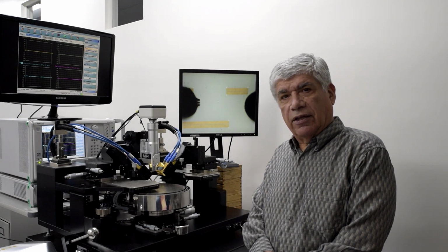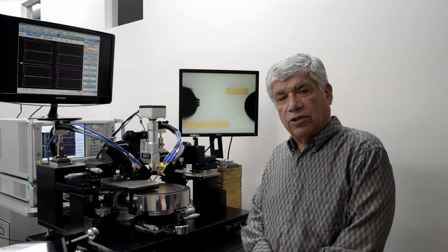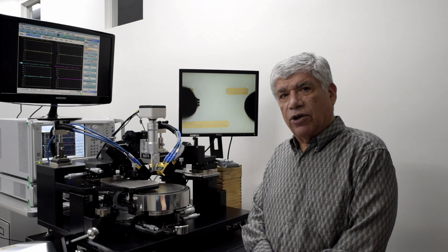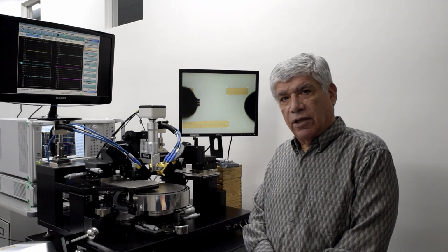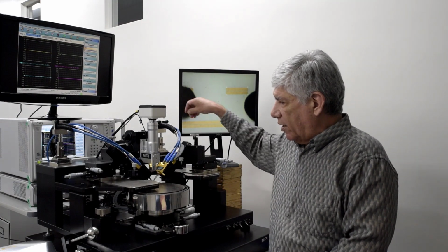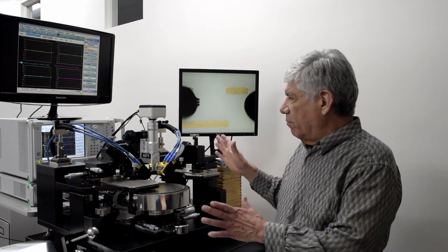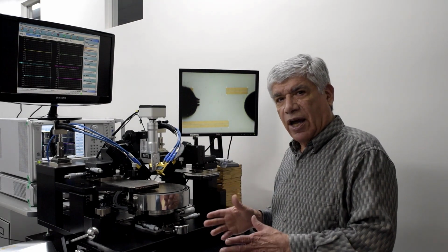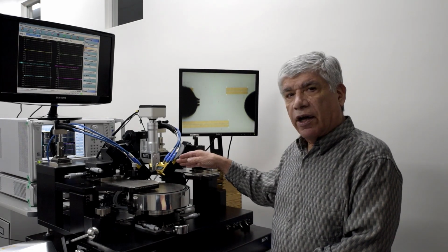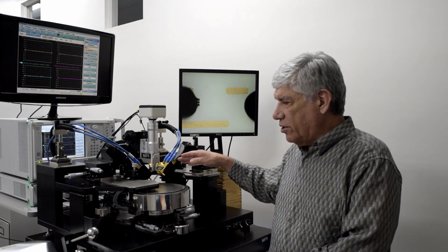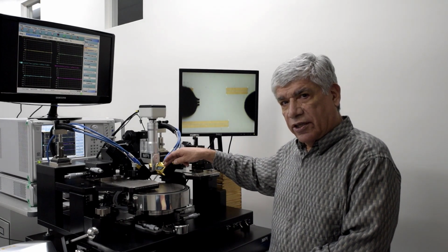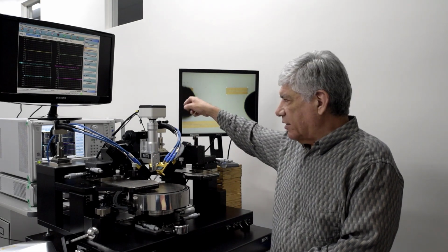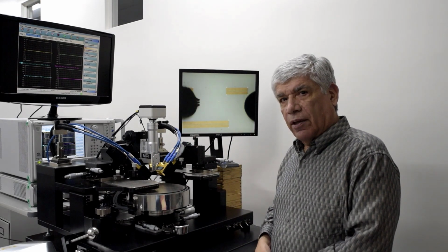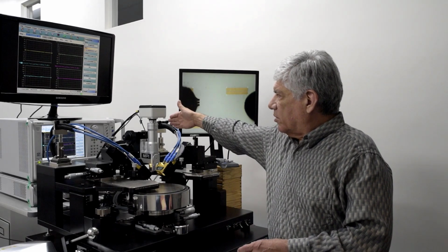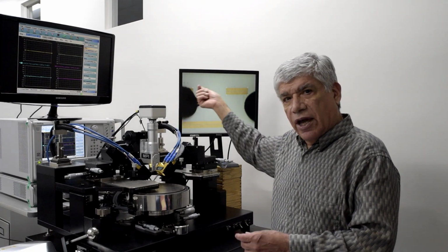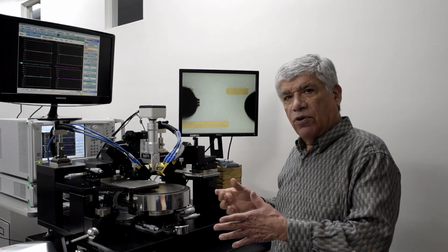Cable movement, especially on the test port cables from the VNAs to the modules, is something to consider as well. So you want to minimize movement after calibration of the test port cables, the interface cables between the VNA and the modules, in order to minimize any kind of movement over a period of time after calibration. However, we did find that because of the nonlinear transmission line location of the test and reference samplers very close to the test port, the effects of interface cable movement is pretty minimal. However, it's still a good idea to use some sort of support mechanism of the cables in order to ensure that the cables do not move after calibration.